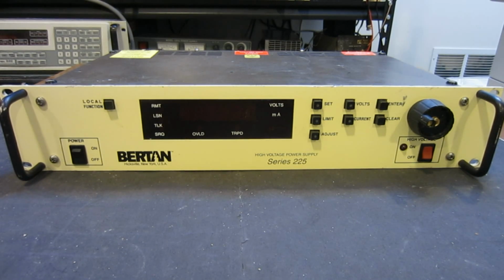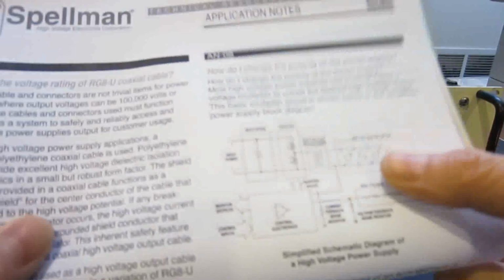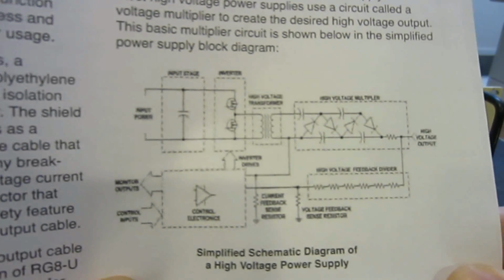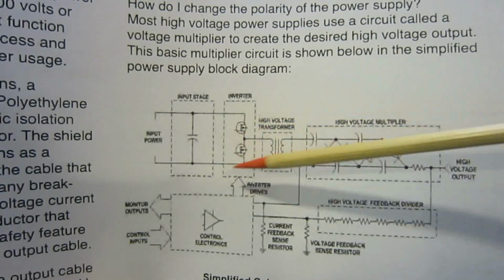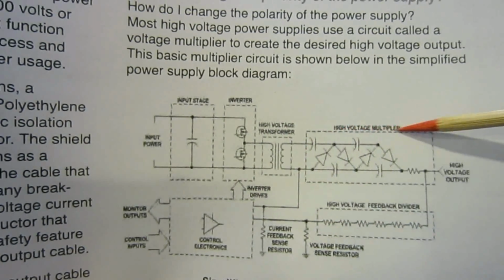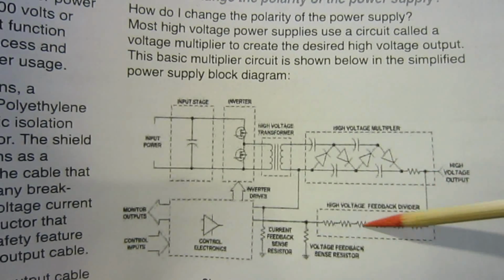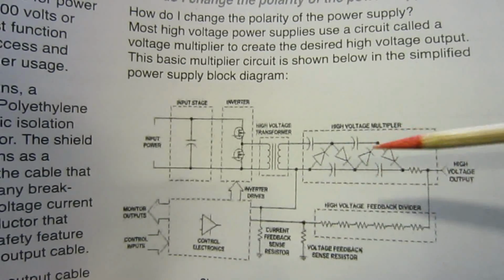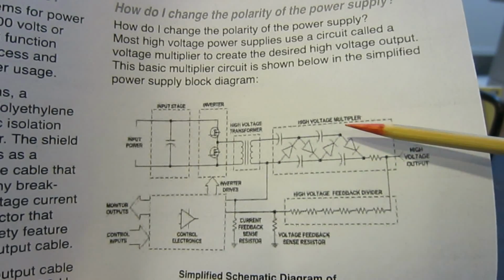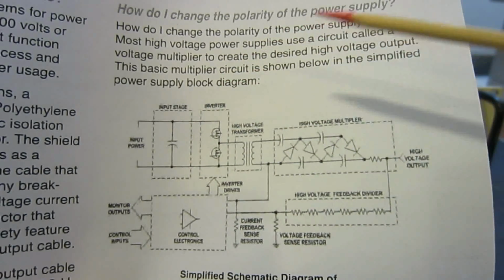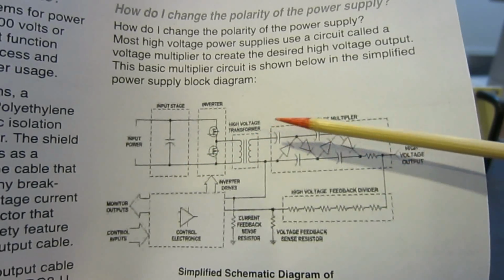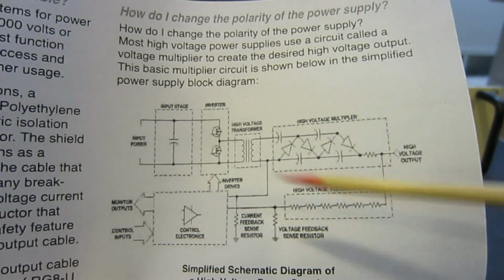Before we proceed to opening up this power supply, let's briefly take a look at the operating principles of this high voltage power supply. Like most high voltage power supplies, a lower voltage is stepped up using some sort of DC to DC converter, and then the voltage is regulated. So let's take a look at Spellman's application note. So here we have a basic diagram, not necessarily the diagram for this particular unit, but you get the general idea. So basically you have a DC to DC converter, and the control voltage is sensed on the high voltage side via either a high voltage divider or some kind of opto isolator. In order to achieve stable high voltage output, you really need a very stable voltage reference, which we will take a look at when we open up the unit. And there also will be some kind of precision DAC and ADC to measure the high voltage.